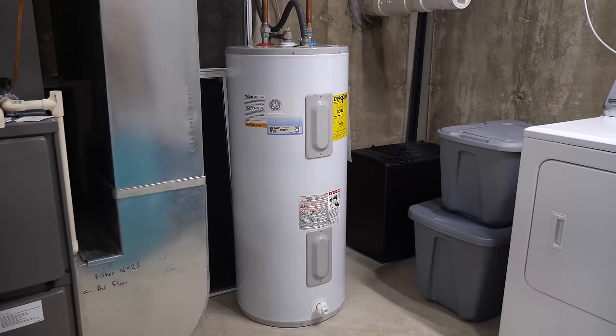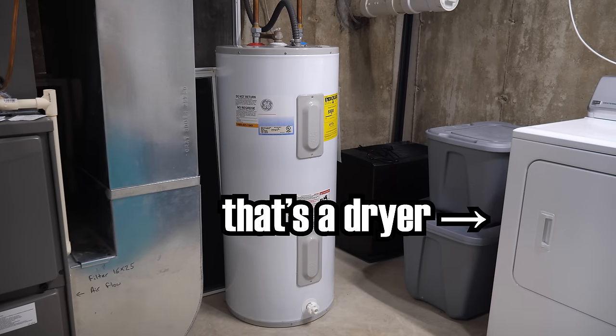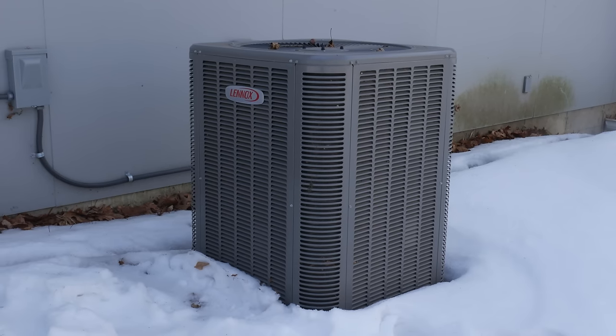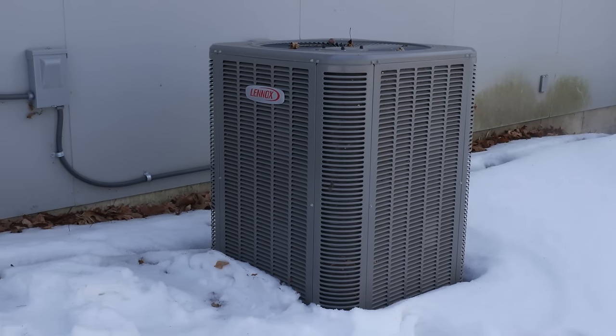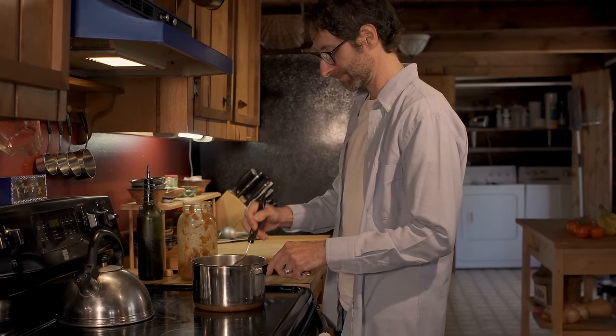However, electric appliances like heaters, stoves, and dryers have to convert electricity into heat, and that takes a lot of power. To give you some sense of their power needs, a conventional electric water heater pulls 18 to 24 amps when it runs. A clothes dryer pulls pretty much the same when you're using it. And a 3-ton air conditioner when it's running? There's another 20 amps right there. Just those three devices pull perhaps 65 amps, and a conventional electric range can pull up to 50 amps. Switch that on for dinner, and now we're at 115 amps — which is too much. We'll trip the main breaker every time we make dinner. So I guess we have no choice but to arrange for an expensive and disruptive electrical service upgrade.